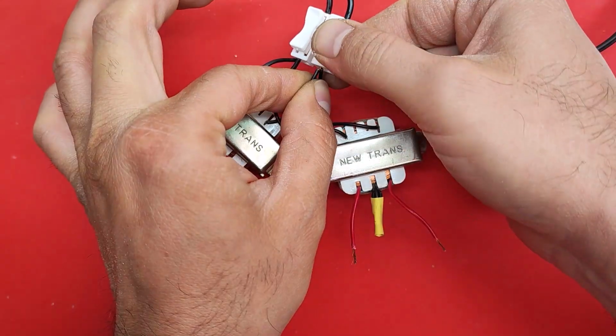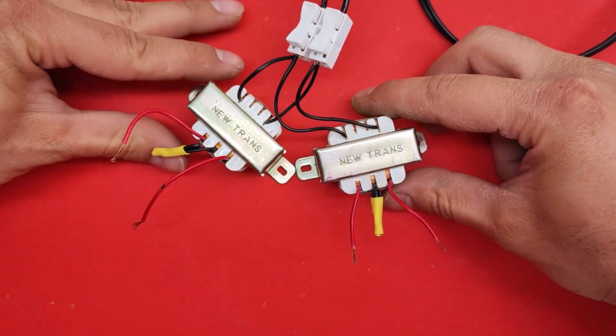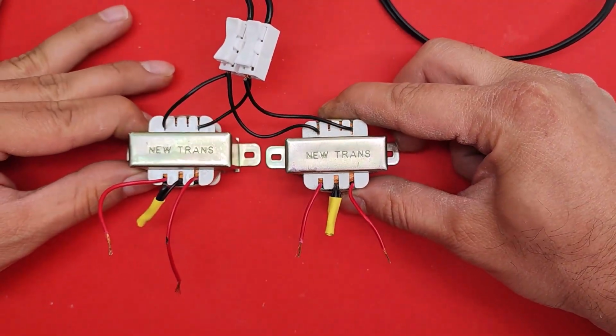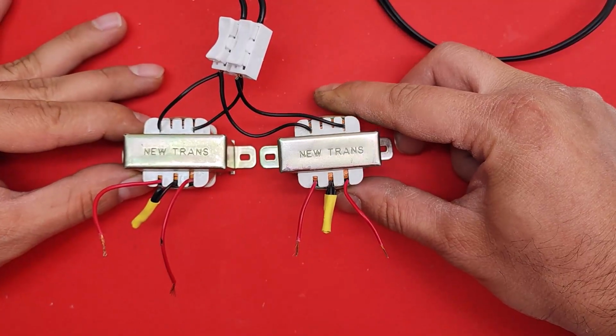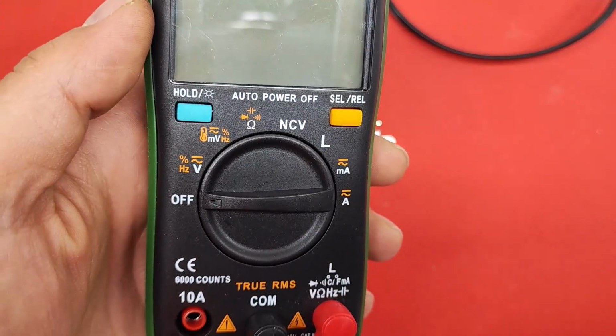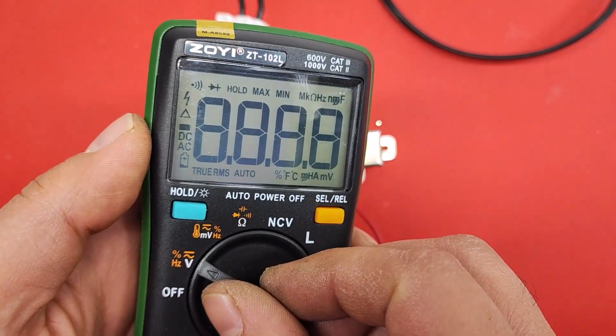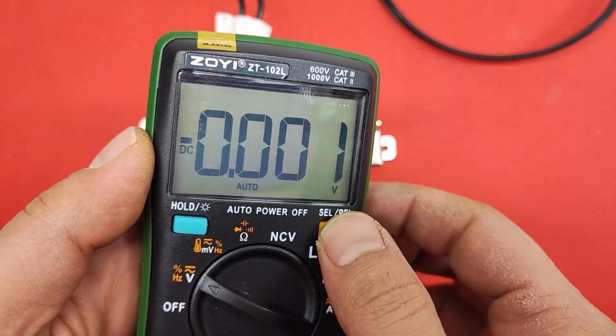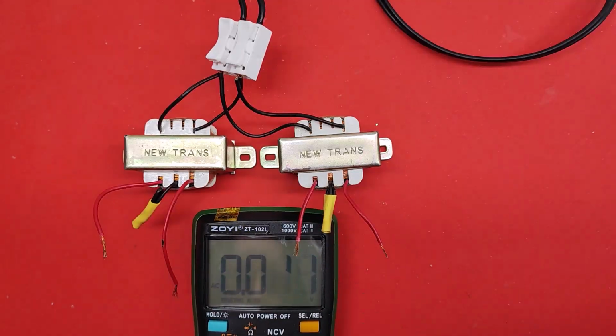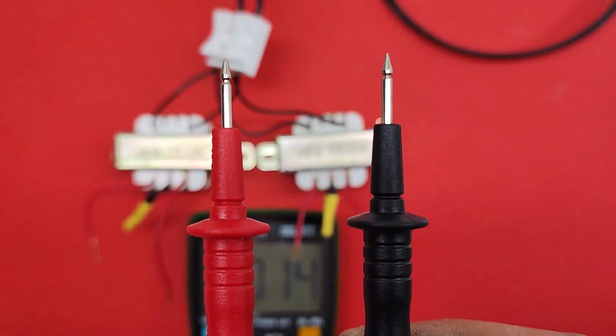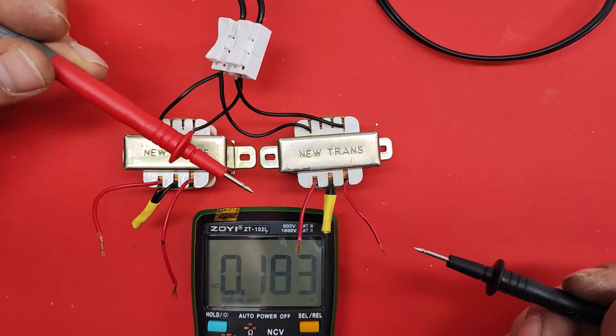Using identical transformers is critical. Different turns ratio or power rating can cause circulating currents, overheating, or unstable voltage. We connect one output wire of the first transformer to one output wire of the second transformer. Then we measure the voltage across the remaining two wires.